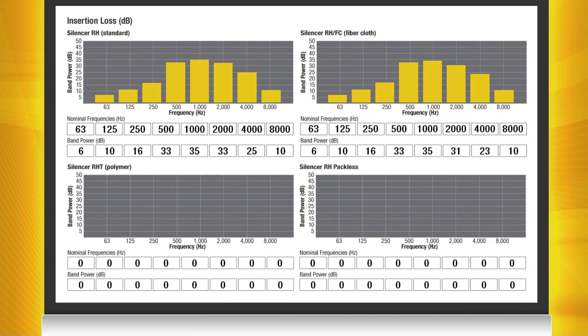As you can see the fiberglass cloth lined unit performs very similar to the standard RH fiberglass silencer. We recommend that you add a fiberglass cloth liner to silencers in applications with high air velocities.